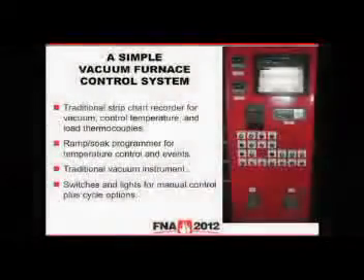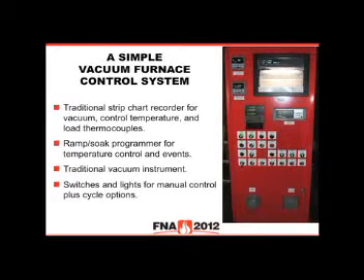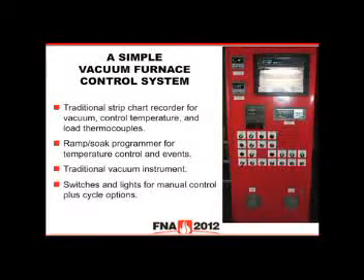This system here is what we would call a traditional basic vacuum furnace control system. These are disappearing and becoming hard to buy — a conventional paper strip chart recorder would record temperature, a load thermocouple or two, maybe five or six load thermocouples, and it would record vacuum level. We would have a conventional ramp-soak programmer to bring the furnace up in temperature at a certain ramp rate, soak at various interim temperatures, bring up to final temperature, and activate a segment to start cooling. We'd have a conventional vacuum instrument, perhaps made by Varian, MKS, or Televac.